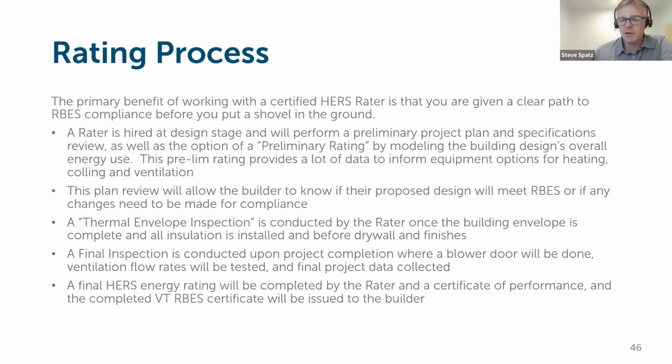So they are required to come out and do, at a minimum, a thermal envelope inspection, which means verifying the as-built of the building envelope before they're closed up, drywall and other interior finishes covering those aspects of the building. The rater is also required to come out upon project completion to perform the required blower door testing and get a verified ACH for the building, as well as verify the flows of the ventilation system and verify that the building was built based on the initial modeling done for the building at project initiation.